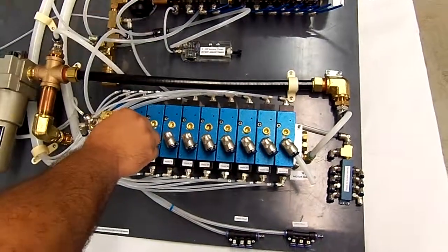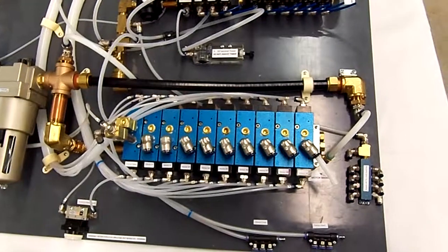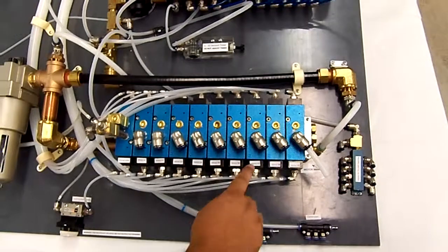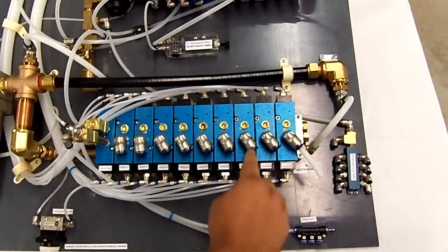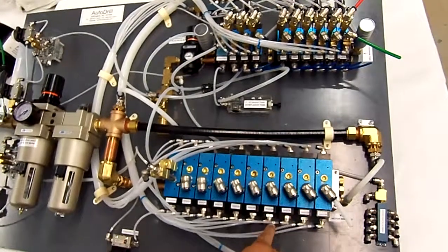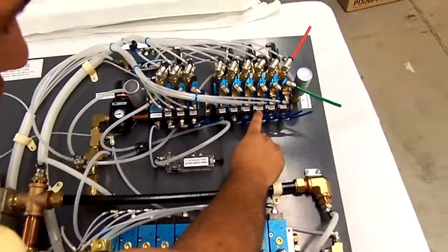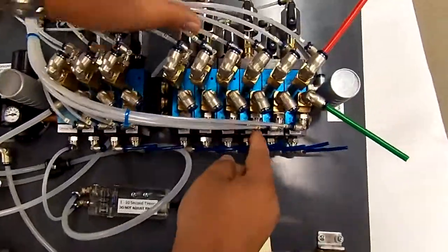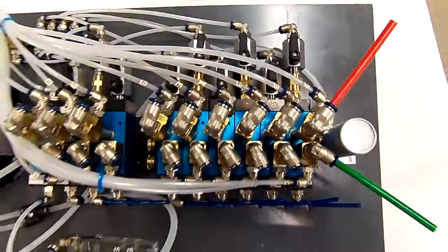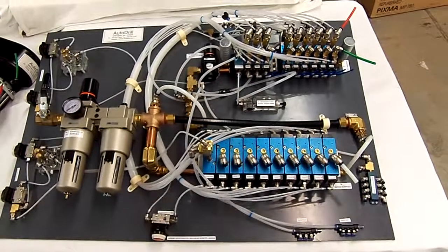Once the supply air goes to all these number 12 ports, it will actuate these drill motors to turn on. If that shutoff valve is off on one of those drills, that particular motor will not turn on. It's critical that these numbers match up with the same valve on the adjacent manifold. If motor seven has a number 16 tube, it's getting supply air from drill seven with a number 16 tube. It's imperative that those two processes work that way.